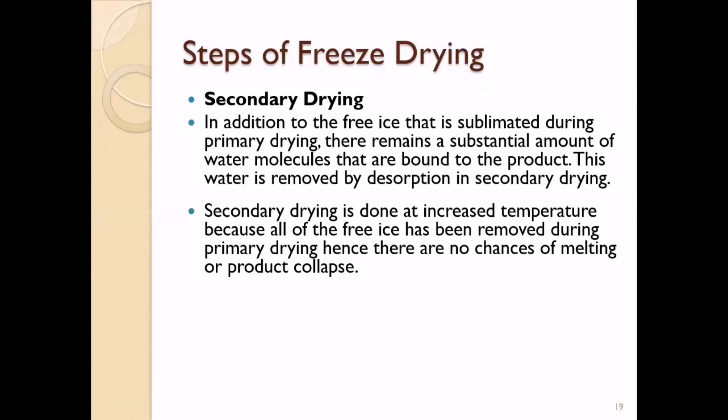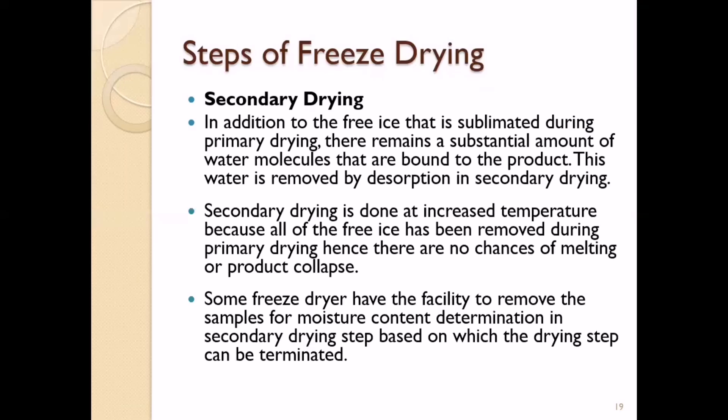The next step is secondary drying. In addition to the free ice sublimated during primary drying, there remains a substantial amount of water molecules bound to the product through chemical bonds. This bound water is removed in the secondary drying process by a method called desorption, whereas primary drying uses sublimation. Secondary drying is conducted at increased temperature because all free ice has been removed during primary drying, so there is no risk of product melting or collapse.